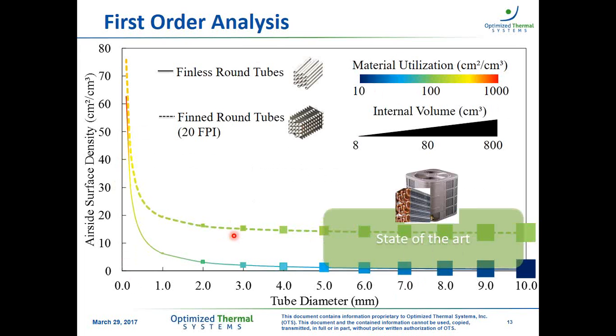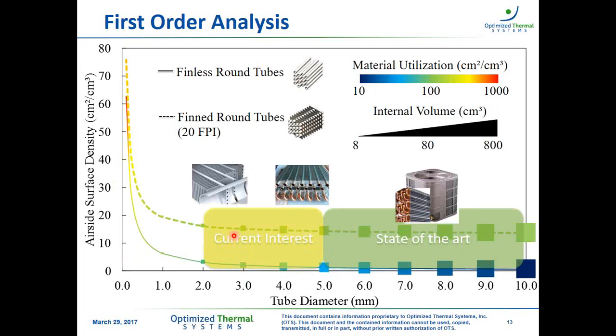What do we know? This is what we know very well, and this is what we have been doing for quite some time now: the state-of-the-art tube-fin heat exchangers with diameters above 5 millimeters. Now, we have a growing interest in designing these heat exchangers with tube diameters below 5 millimeters, around 2 millimeters, as I'm indicating here. I have this additional image of a microchannel, which is the counterpart or the competitor of a tube-fin heat exchanger. Though it's situated somewhere here in this plot, it does have some disadvantages that we'll discuss further on, and why we should pursue tube-fin heat exchangers with smaller diameters.